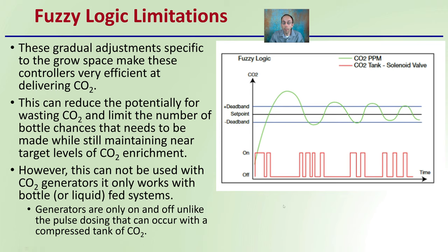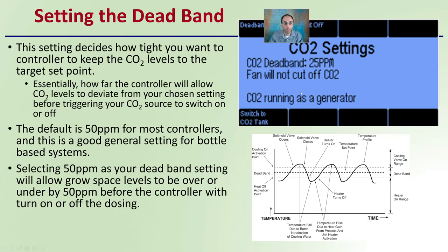We can see an example of pulse dosing here — some pulses are longer, some are shorter. Basically the controller is dialing in and making sure it stays within the target range, ideally staying within the dead band that you've set, which is the amount of tolerance you have to be above or below your actual set point.